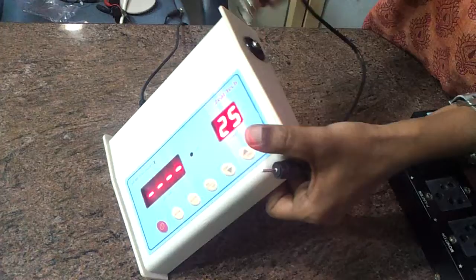Repeat the same procedure for calibration of 9.2 pH and 4 pH by pressing the slope key. Always calibrate with 7 pH first. If one tries to calibrate first with 4 or 9.2 pH, the display will show pH 7. It means start the procedure with 7 pH first. Press the asymmetric key for 7 pH and the slope key for 4 or 9.2 pH. If a wrong key is pressed by mistake, the display will show an error.